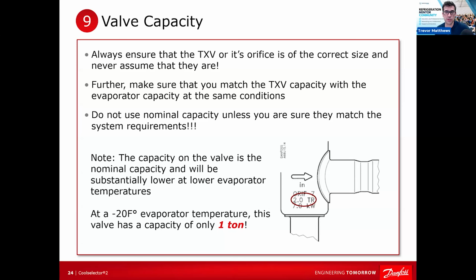And I've seen it before too, where from the manufacturer, it was the wrong valve. So the back pressure was super high, right? A super high back pressure or suction pressure. Some people say back suction pressure. It's really high because the orifice was too small in it. So it's amazing how that works if you're going to underfeed.